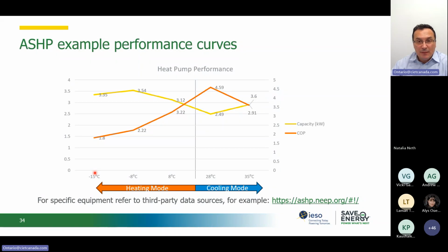But still better than, if you remember the efficiency of the heating system based on combustion devices, fuel combustion devices, we had only 40 to 85%, depending on the efficiency of that system. So we compare 85% with 1.8, which is equivalent to, say, 180%. I will call it again efficiency in quotes because, again, we can't really have efficiency over 1. We can see now that manufacturers are really good in designing their systems. Capacity is fairly steady over the time. The equipment is actually able to provide the sufficient heating for the space. It's just that it's not reaching that beautiful efficiency of 4, 5, even 3 COP of 3.